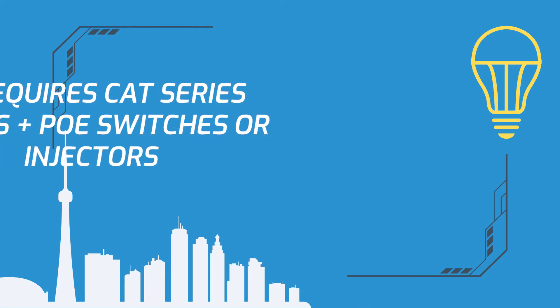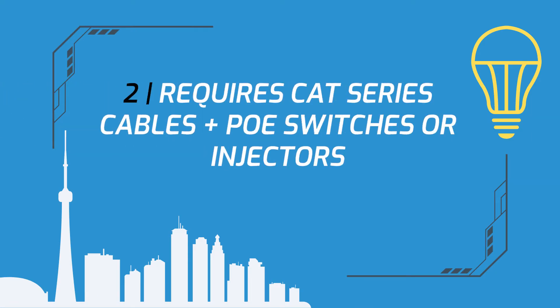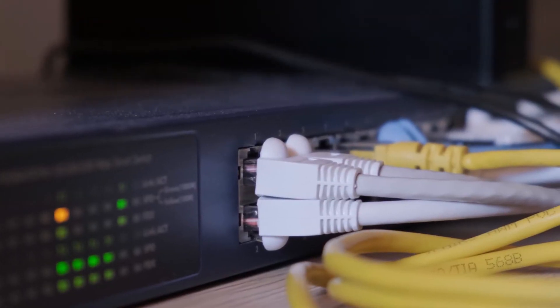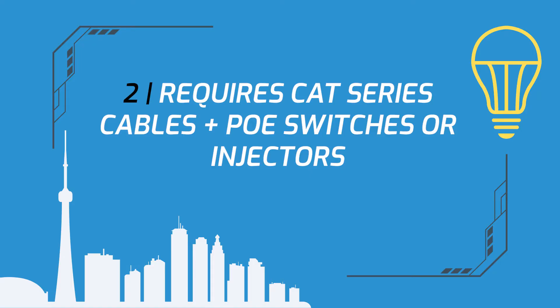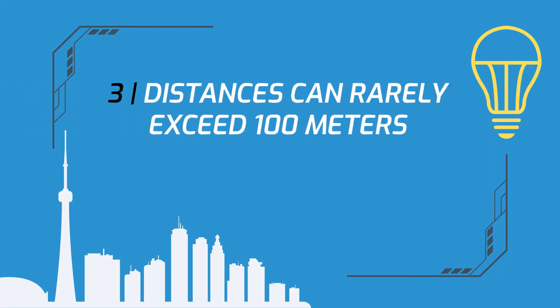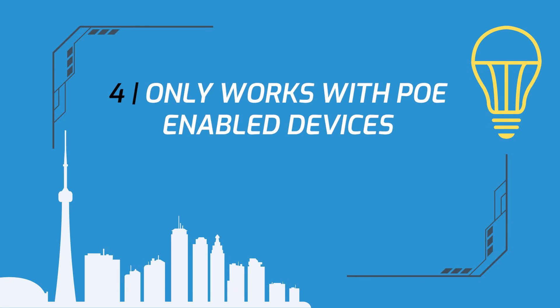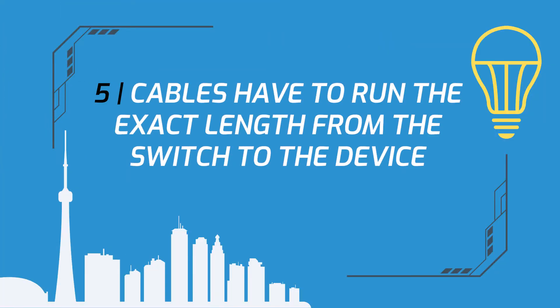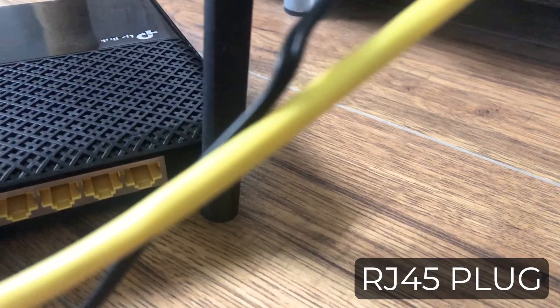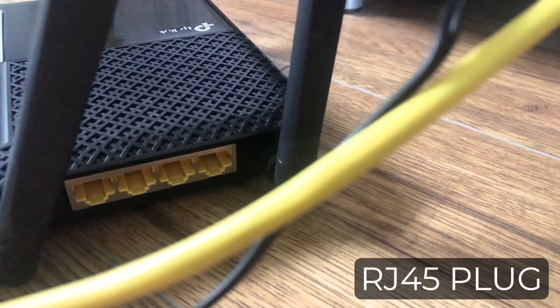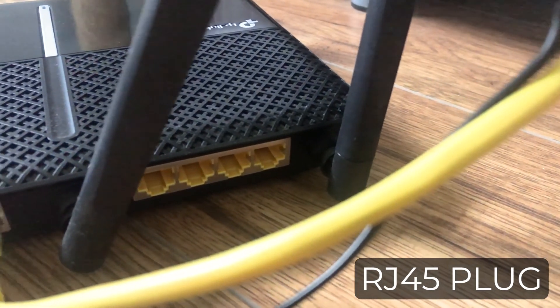Installing PoE can also be expensive for lighting because it requires special CAT series cables with thicker copper gauges, as well as PoE switches or injectors. Also, because it's a low voltage system, distances can rarely exceed 100 meters due to voltage drops along the cable. PoE only works with PoE-enabled devices, so light fixtures must be compatible. Cables in a PoE system also have to run the exact length from the switch to the device, meaning cables must be stripped, cut, and terminated with an RJ45 plug — making installation pretty time consuming.